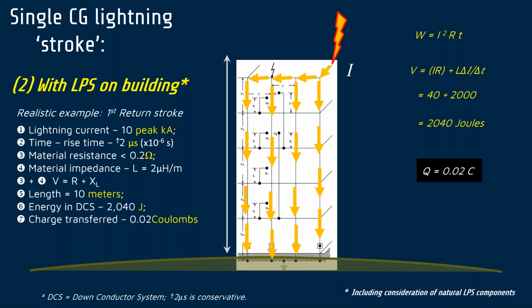And all the current will be flowing in those conductors down to ground. So just before I go to the coulombs, the essence here is that the standard says you must have at least 2 down conductors on any structure. The reason for that is that you obviously have a backup, but we must have current sharing. The extent to which you have more down conductors is based on the lightning protection levels, which are deemed to be directly related to the lightning current.